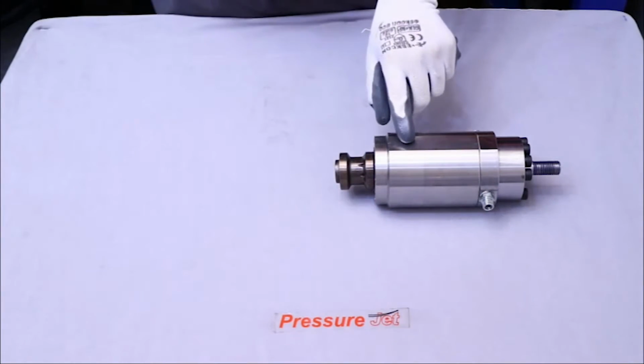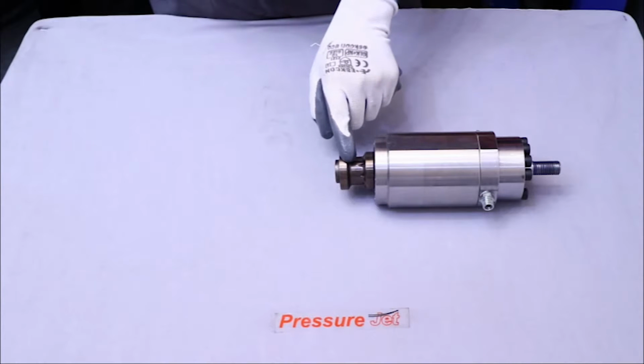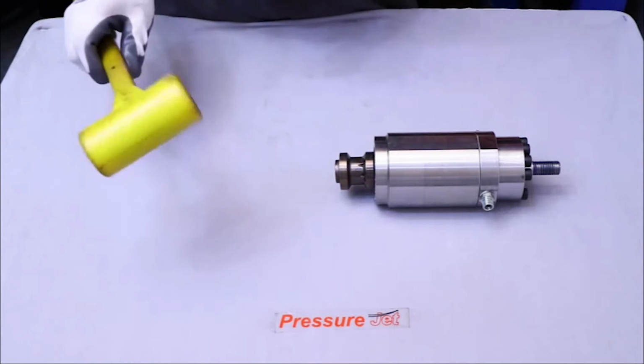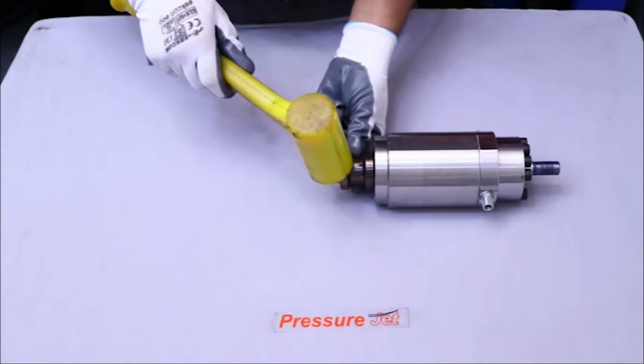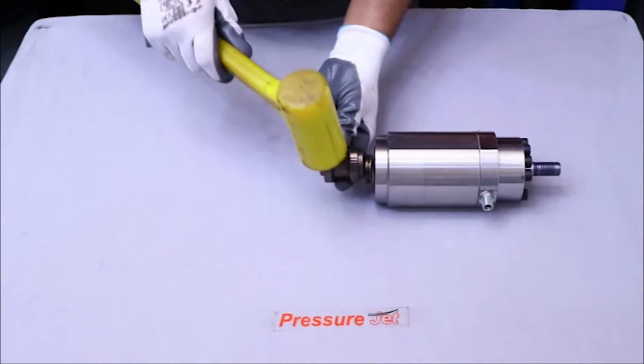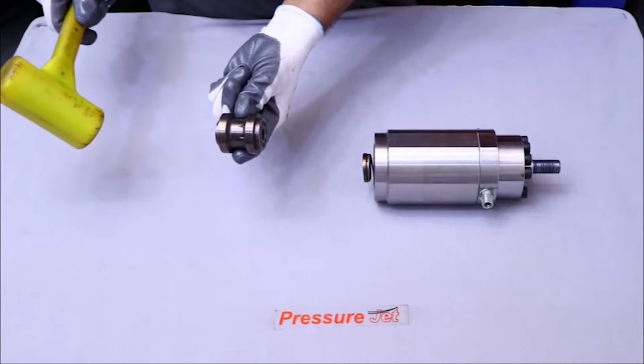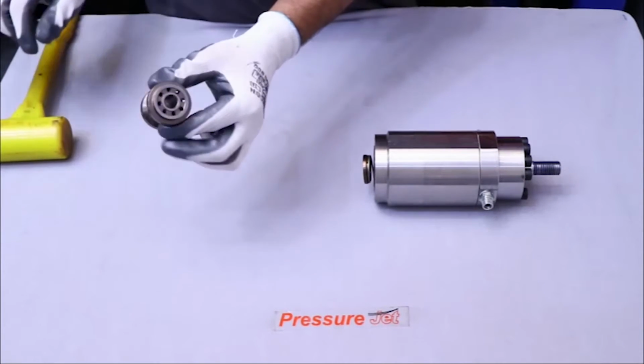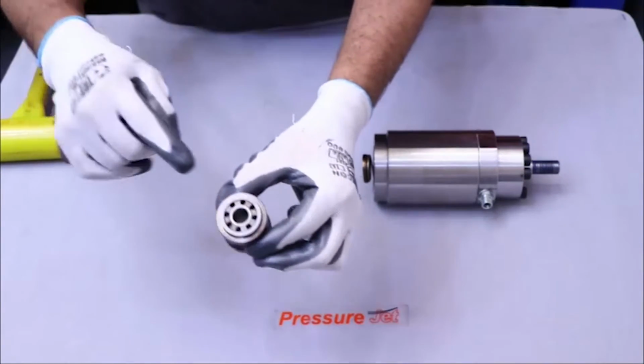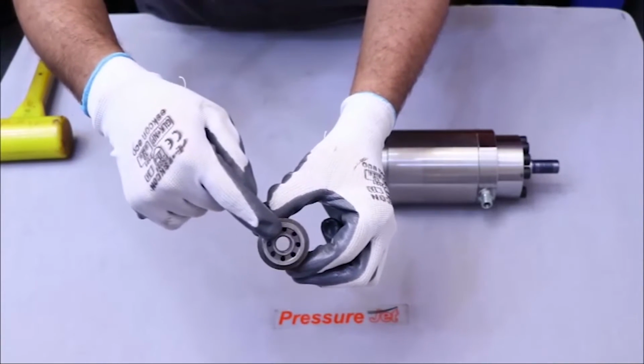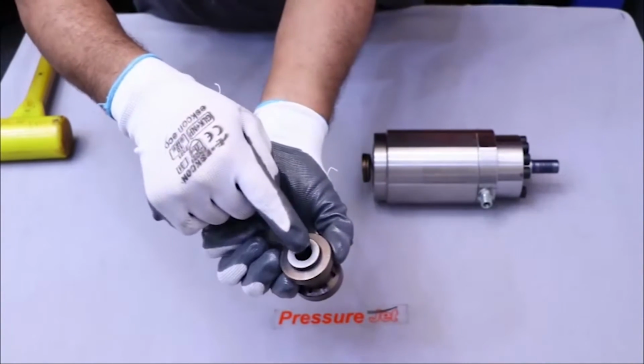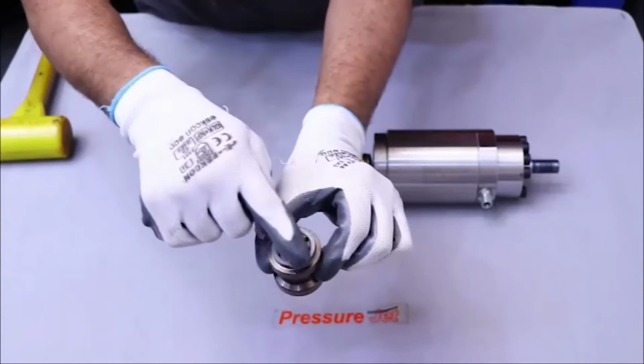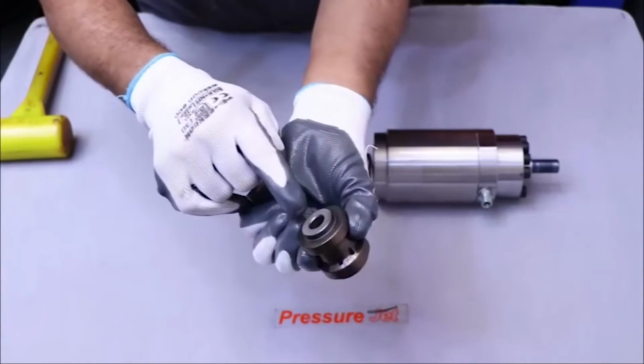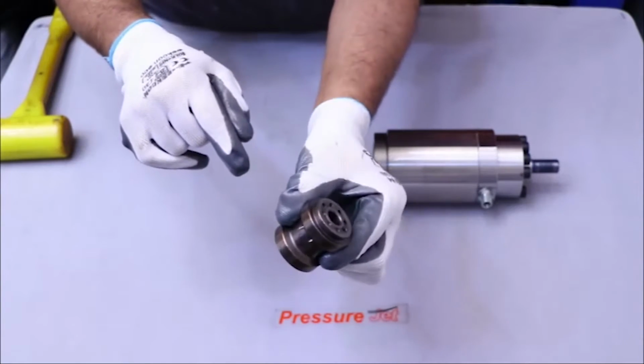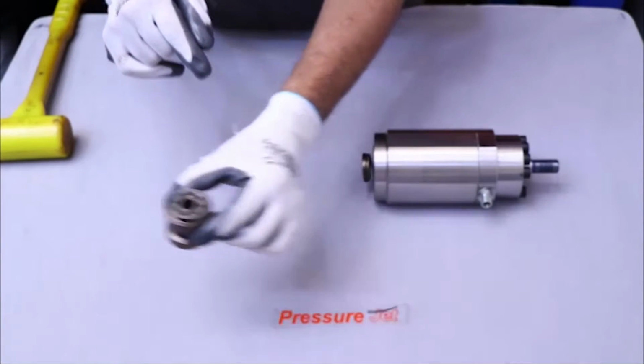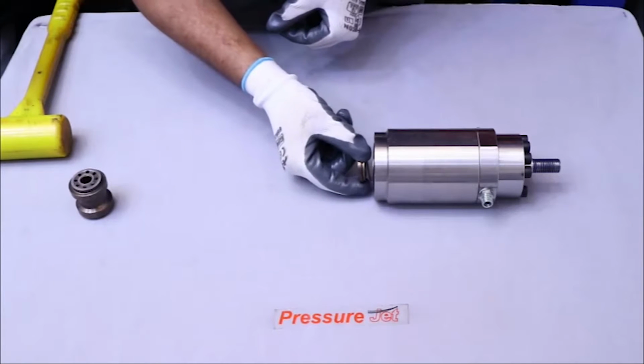Put stuffing box assembly on a clean surface. To start disassembly of stuffing box assembly, remove suction and discharge valve seat from the stuffing box. Gently push it by rubber hammer. Inspect the flat surface of suction and discharge valve seat from both sides, and it should not have scratches. Note, if it has scratches, then do lapping on its surface or replace it with a new one.